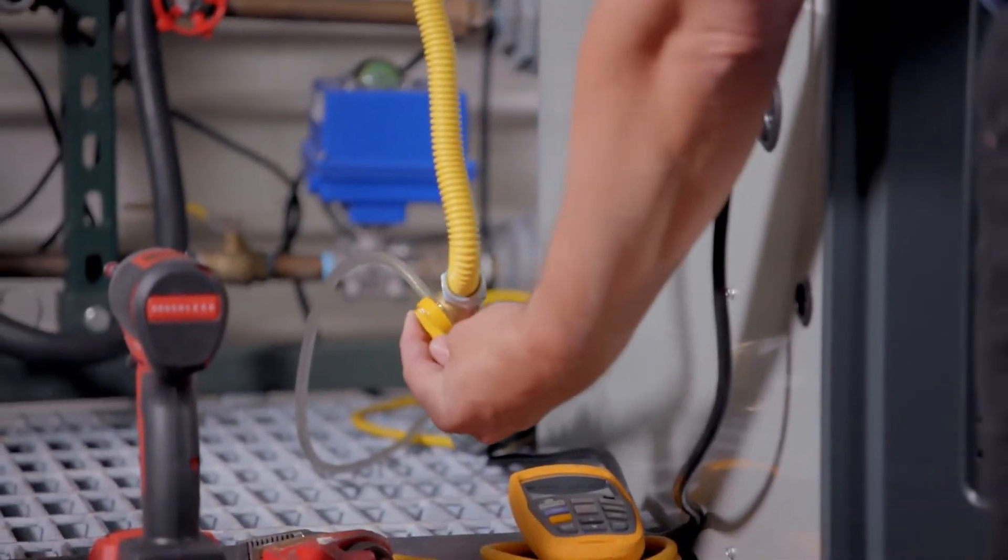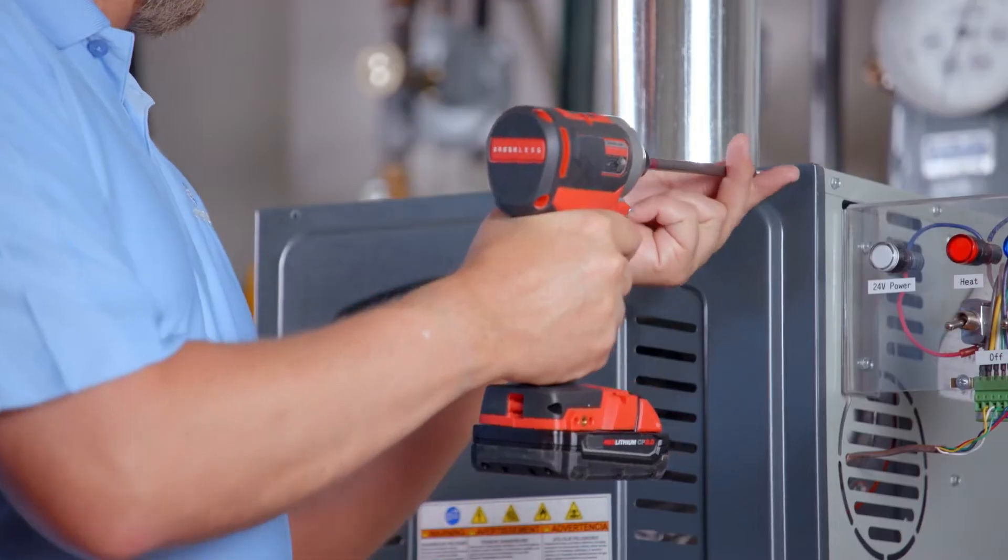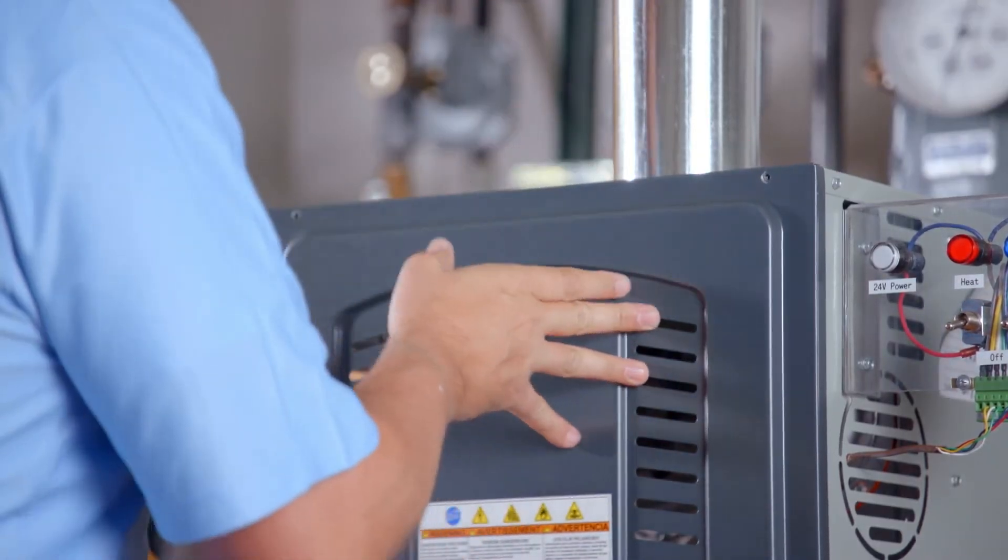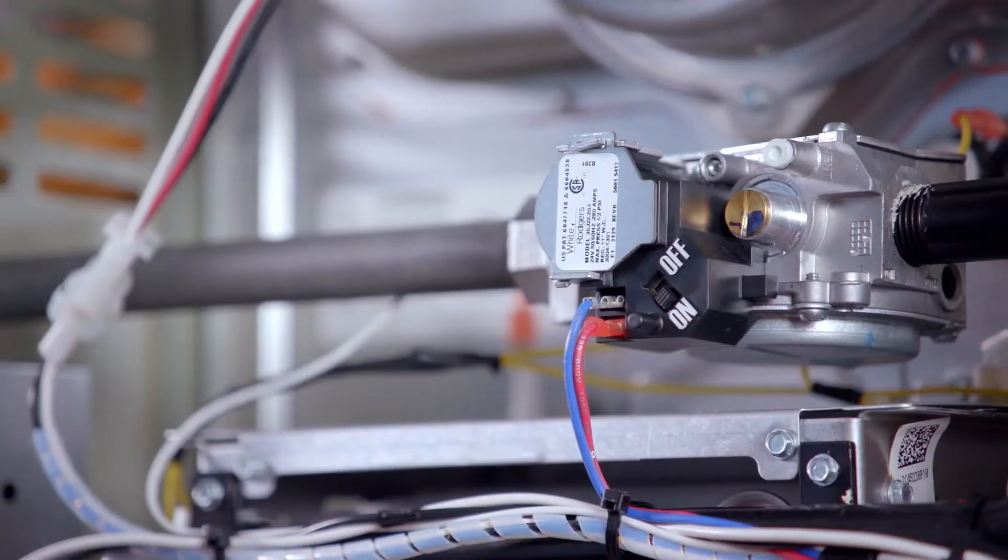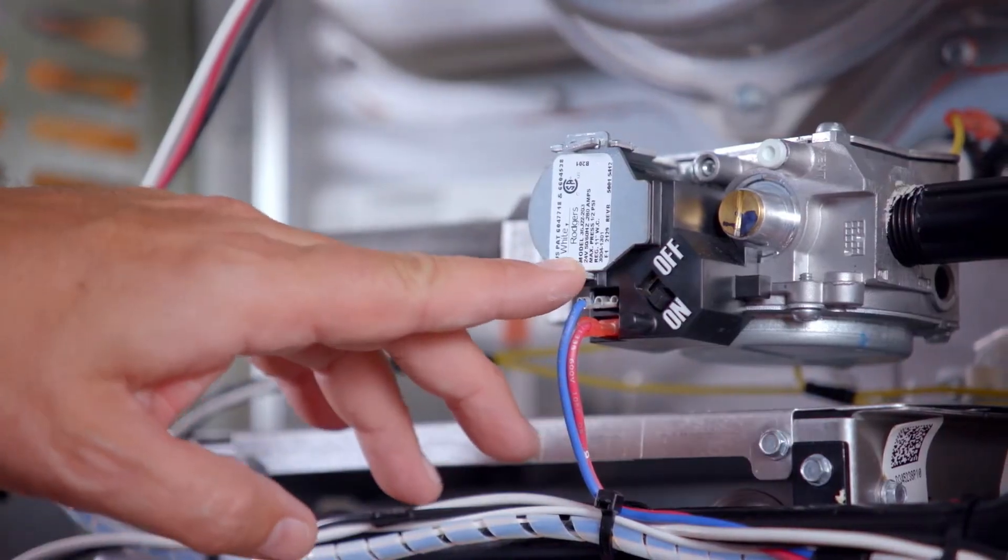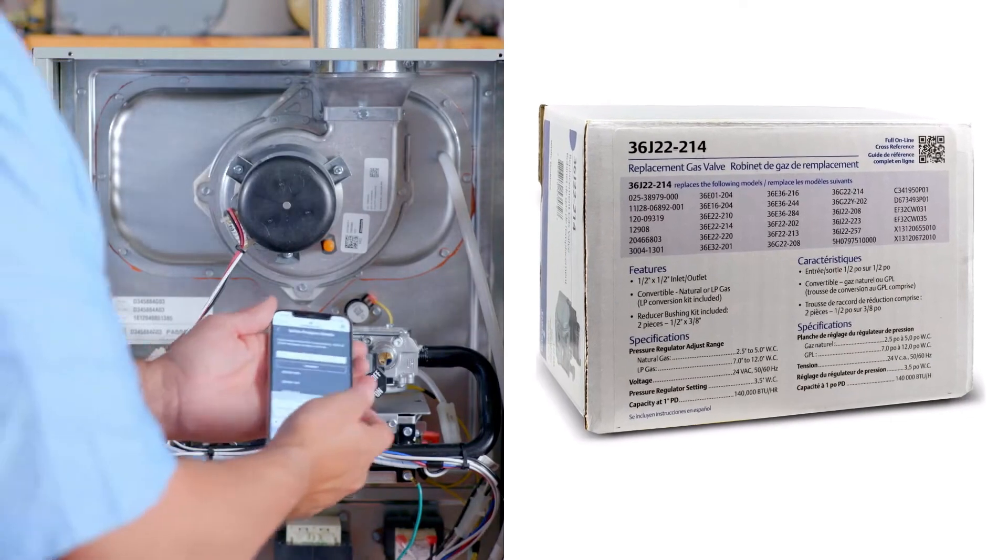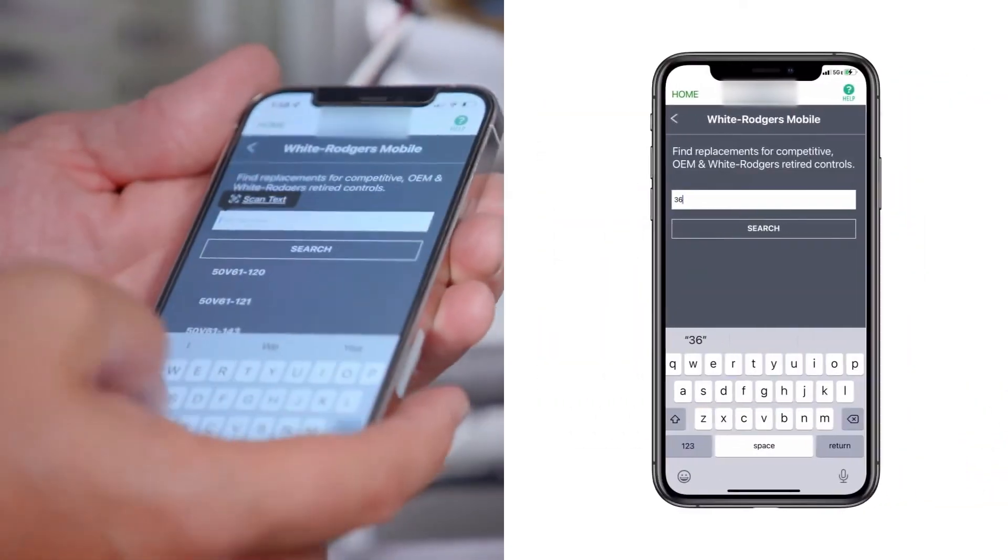First, ensure power and gas are disconnected prior to servicing the unit. Remove the access panel. Check the part number on the existing gas valve and verify it can be replaced with the 36J22214 Gas Valve Kit. Use the cross-reference table on the side of the carton or the White-Rodgers mobile app.